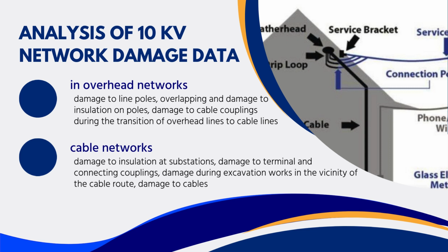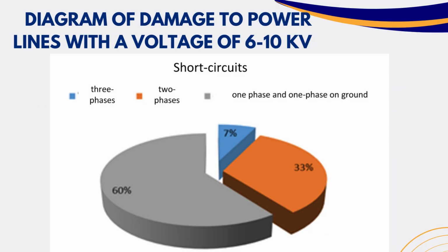But if you analyze 10 kilovolt network damage data, it is necessary to classify it into 2 types. First, the overhead network, second, the cable network. For the overhead network: damage to line poles, overlapping, damage to insulation on poles, damage to cable coupling during the transition of overhead lines to cable lines. These are the more common ones for the overhead network. For the cable network: damage to insulation of substations, damage to terminal and connection couplings, damage during excavation work in the vicinity of the cable route, damage to cables, and so on. In wartime, the overhead network can be more damaged, but in the cable network it is more difficult to understand and find the place where it is damaged, and the cables are also quite old and not changed a lot.